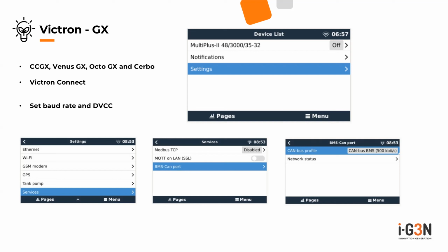You connect your battery to the VE.CAN port, then connect via Victron Connect and set two settings: baud rate and DVCC. Go to settings, services, CAN bus port, and baud rate, and select 500 kilobits per second for all iGen products.